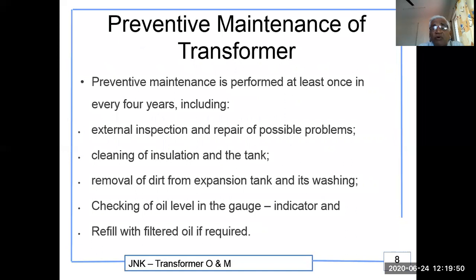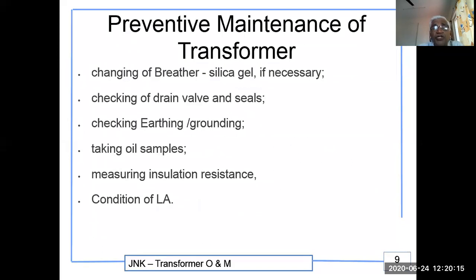Preventive maintenance of a transformer is performed at least once in every 4 years, including external inspection and repair of possible problems, cleaning of insulation and the tank, removal of dirt from the expansion tank and its washing, checking of oil level in the gauge indicator, and refilling the filtered oil if required. Changing of the breather and the silica gel if necessary, checking of the drain valve and seals, checking of earthing and grounding connection, taking oil samples, measuring the insulation resistance and condition of the lightning arrestor.